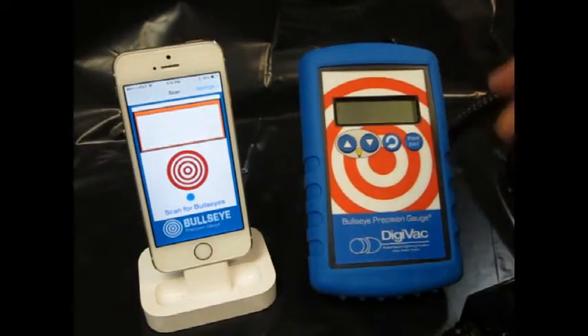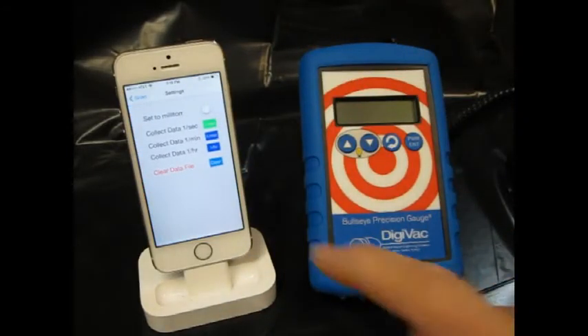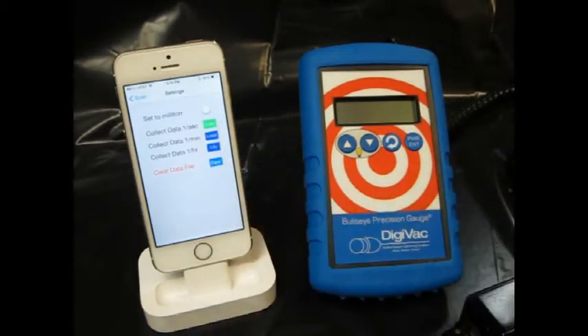Let me turn off the device for a second. In the app we do have some settings where we can display the vacuum readings in either Millitorr or Microns.